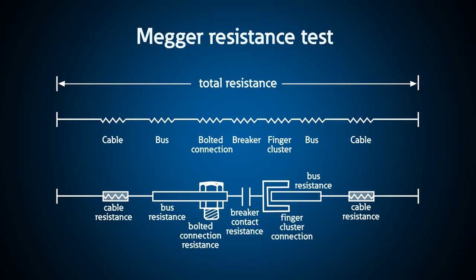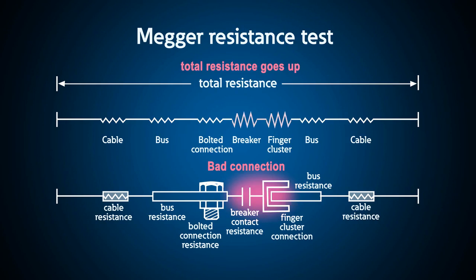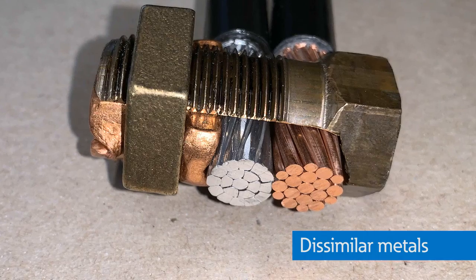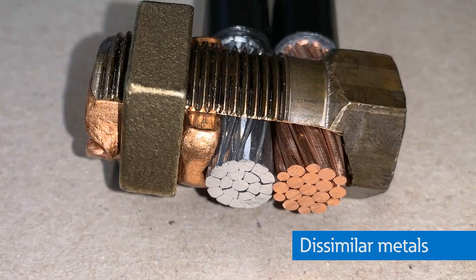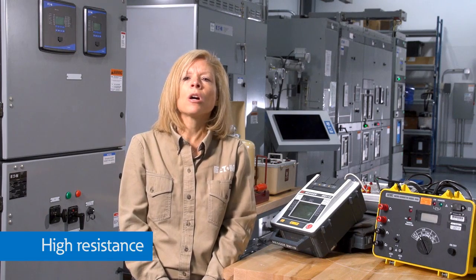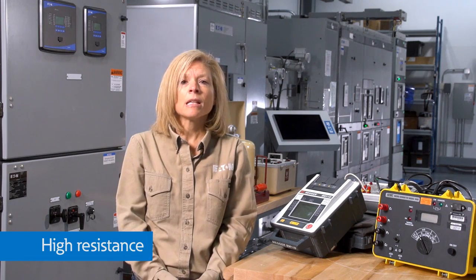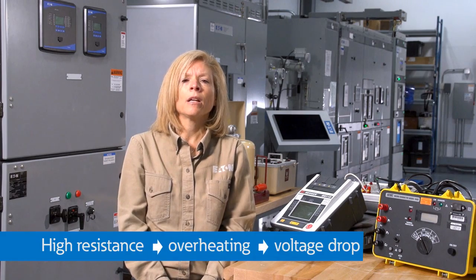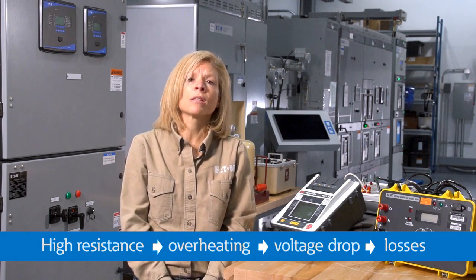This resistance is added to the total resistance of a system, so typically it is better to have a low measured value. Some things that may contribute to bad or high ductor readings may be dirty or loose connection points, or dissimilar metal bonds like copper and aluminum. High resistance at electrical contact points or connections typically result in overheating, voltage drop, and losses.